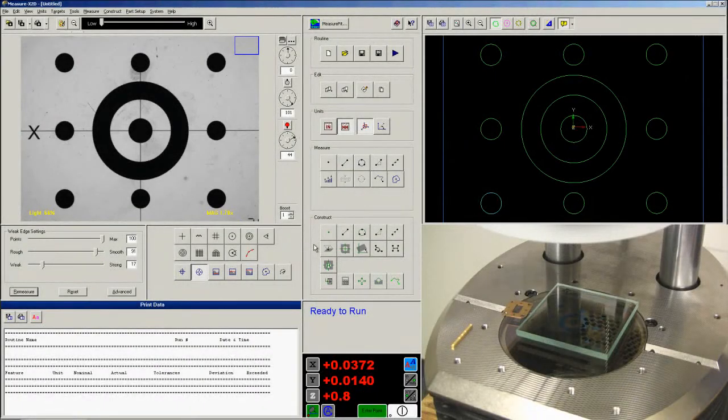Now the digital image that we are seeing is roughly 2 inches. It's about 2 by 2 area. And when we go to high mag, we can pan the entire area. We can measure at low and high mag the entire area. We're not forced to measure near the center.